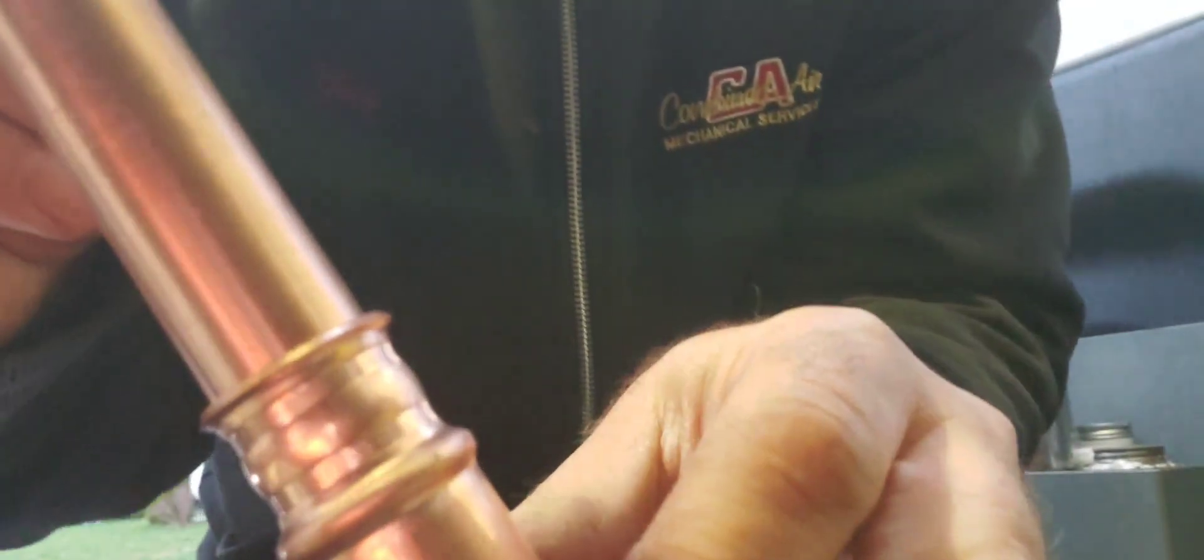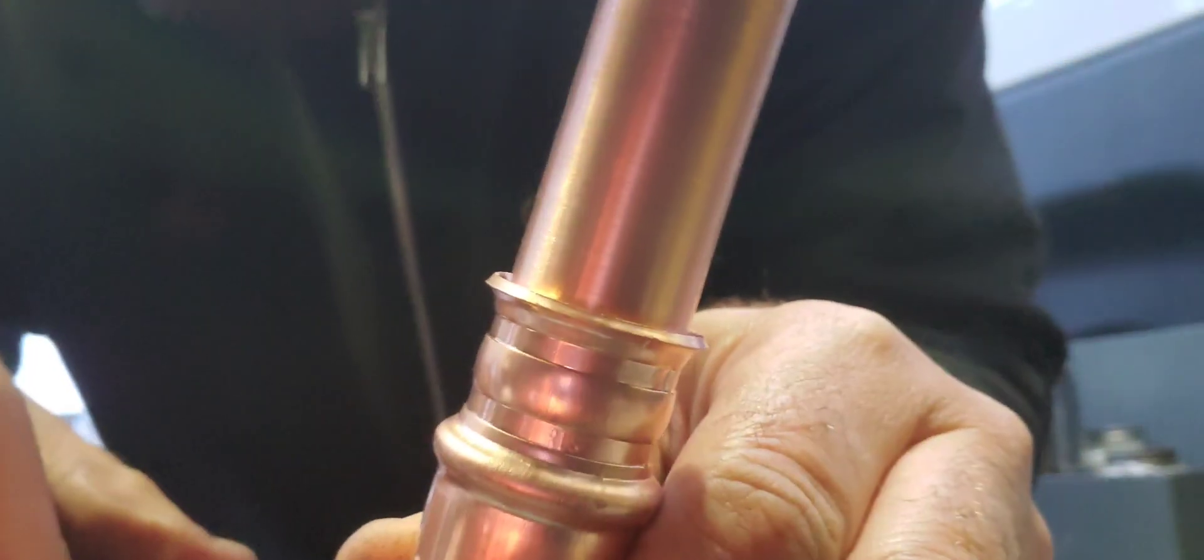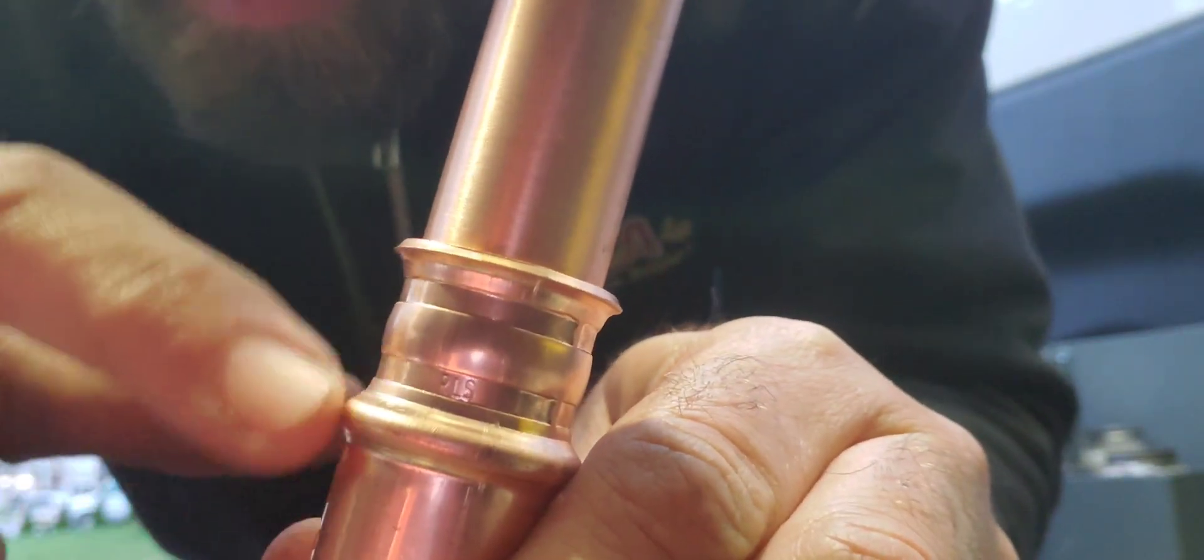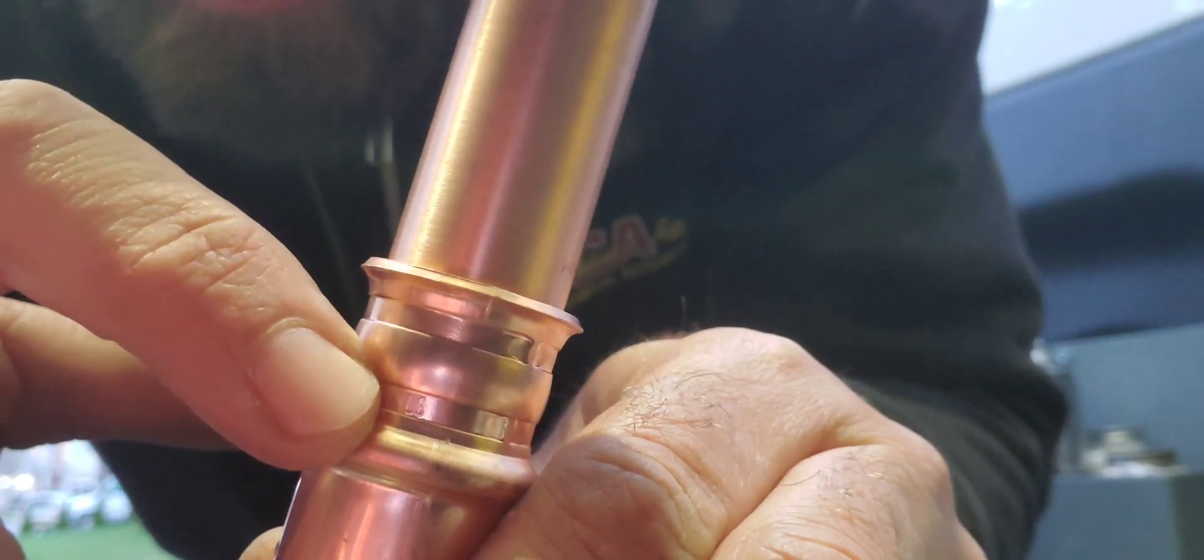One important thing you've got to look for here is the RLS stamp right there. That lets you know that it's properly pressed. Pretty cool. So next we use the crimp gauge.